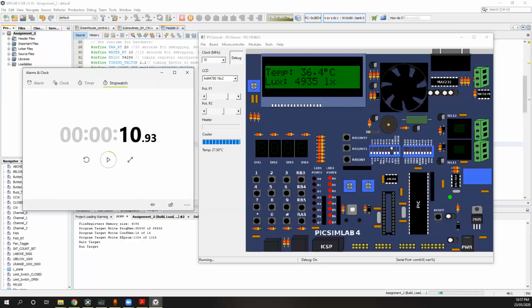The next requirement is that the sprinklers are triggered once it rises through the maximum temperature set point, which is in this case 40 degrees. I would like to mention the buzzer will go off with this one as well, so I'll turn that one off as soon as I can so you can still hear what I'm saying. I'll get right up against that boundary. That's pretty close. All right, and go. All right, so the sprinkler's on. I did turn that buzzer off, yep.